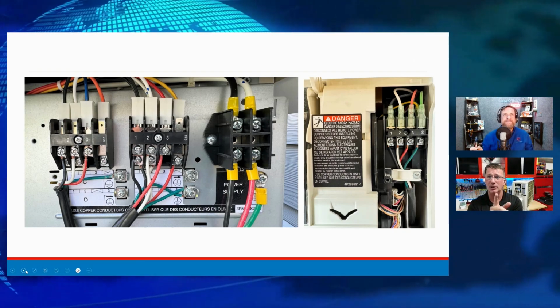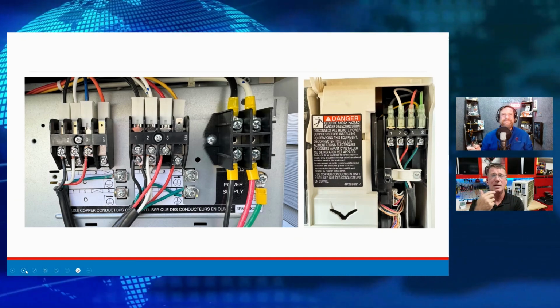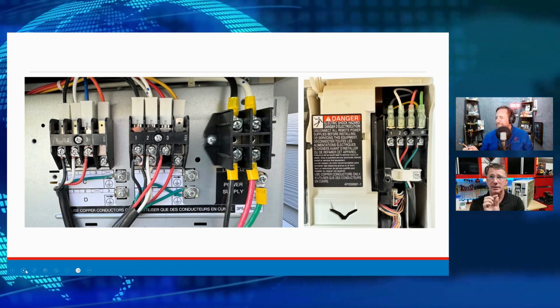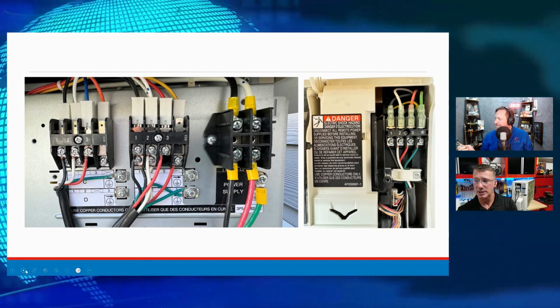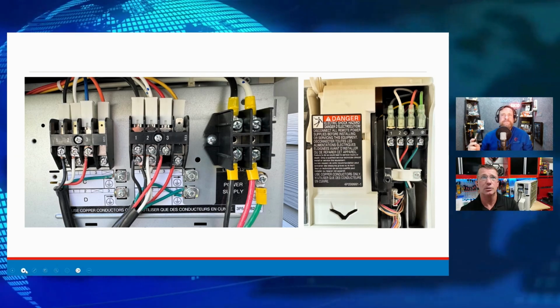That's the reason we label those like this particular. This is the one that I use here for the shop and for the garage and the wood shop. So this is a 3-ton 4-port. So it has A, B, C, and D. Critical that the A from the outdoor unit is connected to the A indoor unit all the way through those. So I'm actually just using 3 heads on this particular installation. But the wiring is 100% crucial on that.